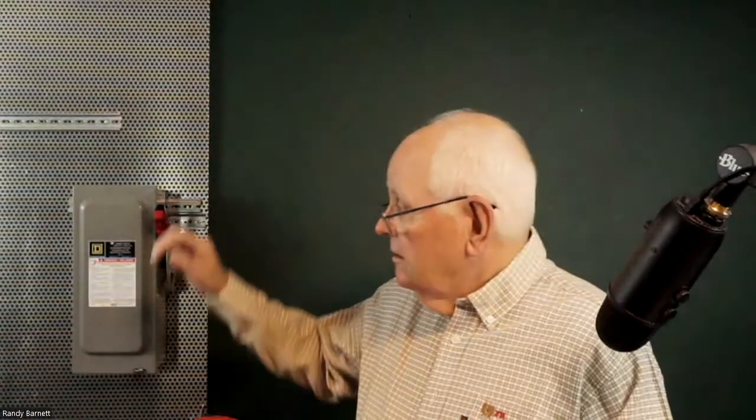Removal or installation of circuit breakers or switches. No, we're not removing anything here. Applications of temporary protective grounding. No, we're not doing anything like that. Oh, how about this one? Operation of a circuit breaker, switch, contactor, or starter. This is a disconnect switch. I want to pull the handle down. So that's operation of the switch. So that task would apply then.